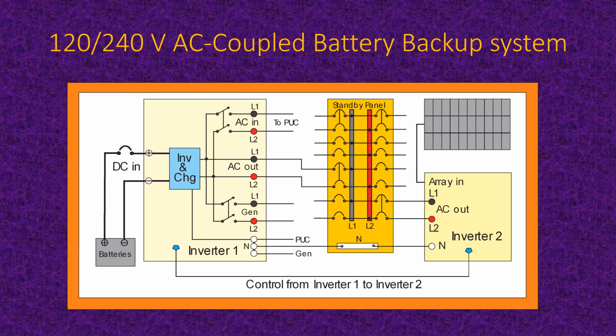And that's part of the point for any inverter when you've got two of them like this, and particularly when we're talking about Enphase. So that's why we're getting to the answer to that question about whether this works with Enphase. The answer is yes. But the Enphase microinverters have to be of the IQ7 and IQ8 series, so that they can communicate with other things that tell them they have to back off. Okay, because the Enphase inverters would be in place of inverter 2 here on this particular picture. Okay, case number 4. So you see one of the cases is the battery is getting overcharged because there's nowhere for excess electricity to go if the utility is down. And so you can see this is where if your array is too big, you're going to waste a lot of electricity if the utility is down.